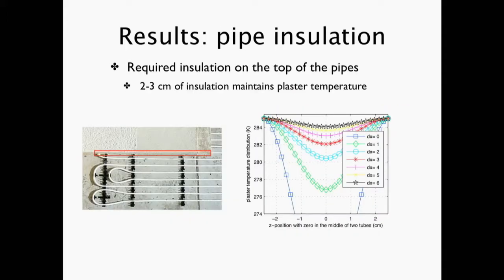Now, the performance of such a system requires some analysis—we needed at least 2 or 3 centimeters, about an inch, of insulation on top of that piping system in order for it to be effective and maintain a uniform temperature.